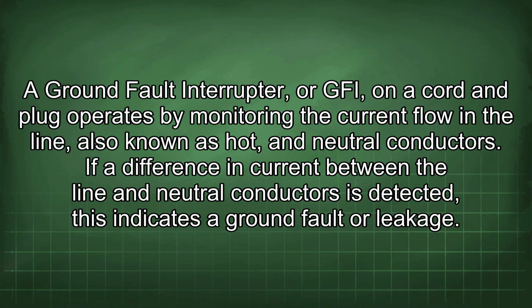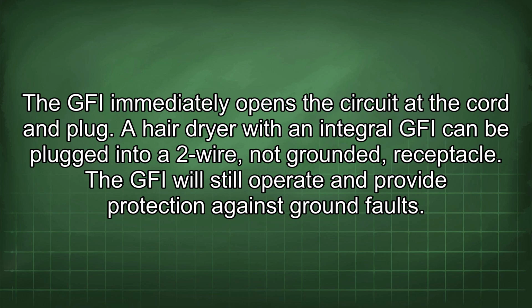A ground fault interrupter, or GFI, on a cord and plug operates by monitoring the current flow in the line, also known as hot and neutral conductors. If a difference in current between the line and neutral conductors is detected, this indicates a ground fault or leakage. The GFI immediately opens the circuit at the cord and plug.